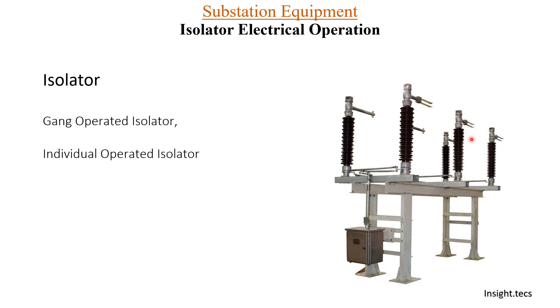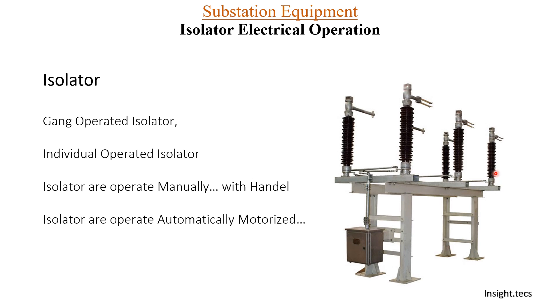Then we have individually operated isolators in which each phase is operated separately. Isolators are generally operated manually with a handle in the switch yard itself. Another way to operate the isolator is automatically — motorized isolators. Motorized isolators have a mechanism inside a box, and they can be further operated in two ways: local operation, which is electrical operation, or remote operation.